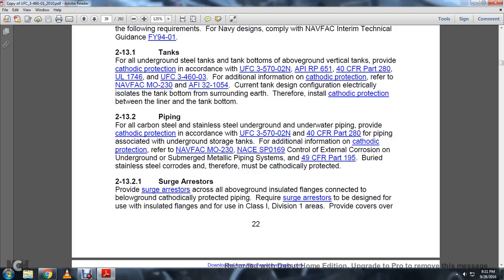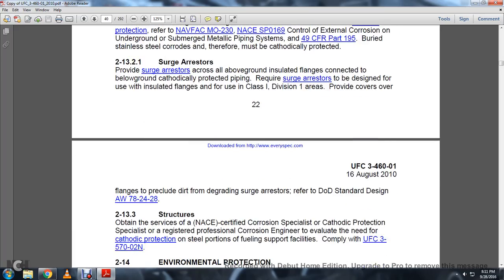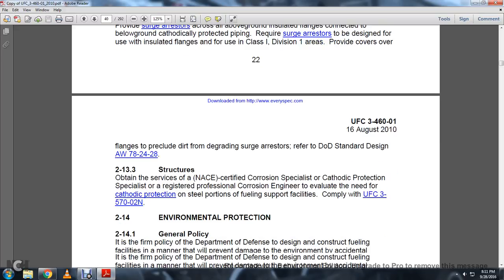2-13.2.1 Surge arresters. Provide surge arresters across all aboveground insulated flanges connected with below-ground cathodically protected pipe. The surge arresters must be designed for use with insulated flanges in Class 1, Division 1 areas. Provide covers for the flanges to preclude dirt from degrading the surge arresters, referring to Department of Defense Standard Design AW 78-24-28.